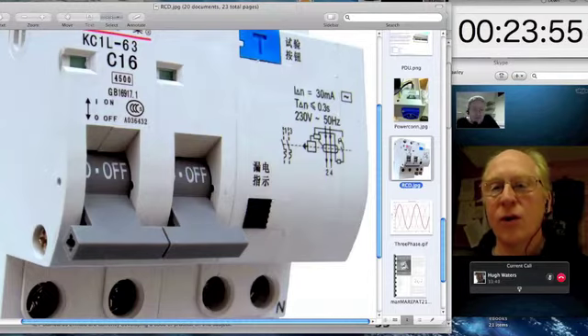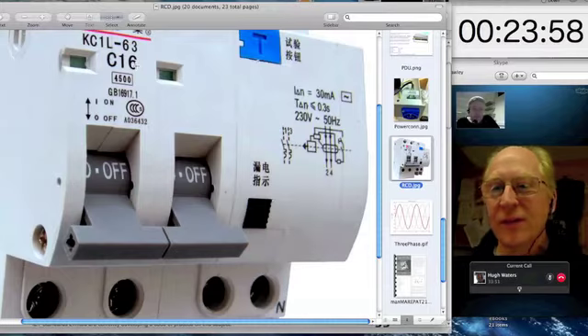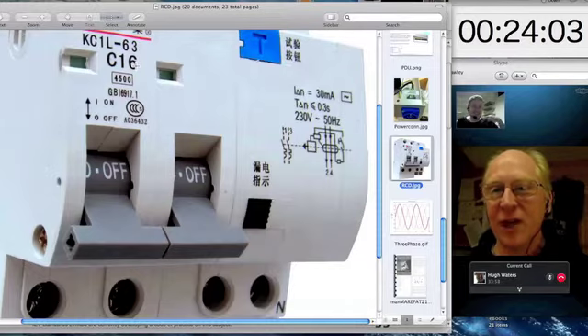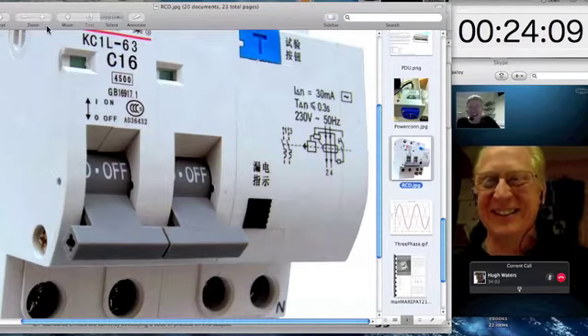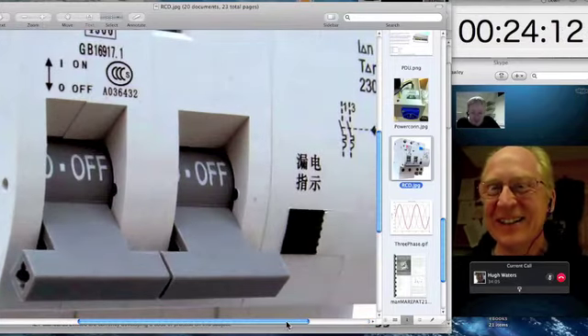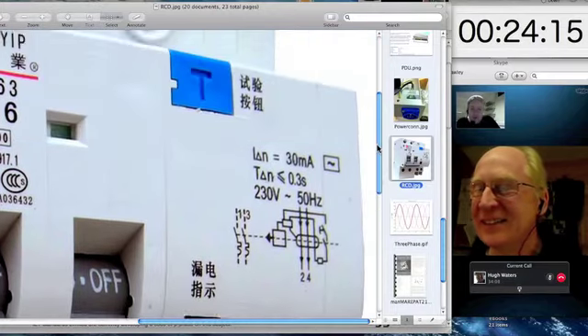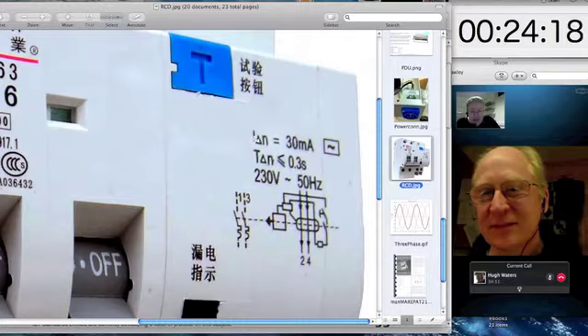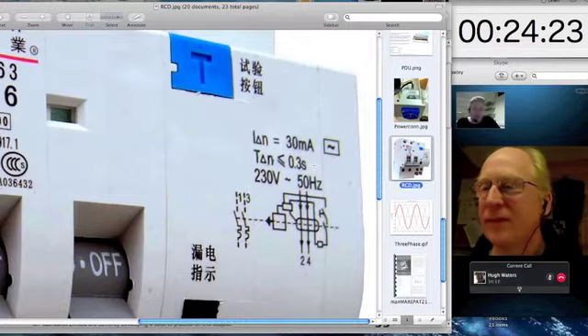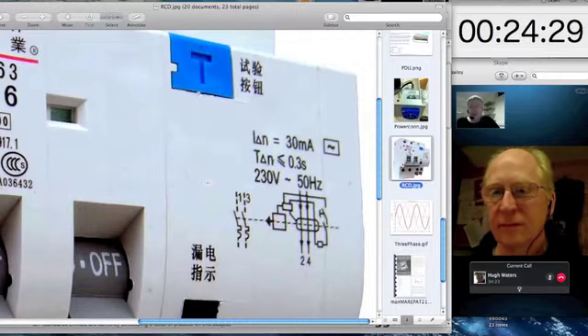And so if you had your hose analogy, you've measured the amount of water going in, you've measured the amount of water coming out. Oh, hang on, less is coming out than is going in. Yeah, therefore there must be a leak somewhere. The floor's getting wet. Got wet trousers. Yeah. And so I'm zooming right in on this, and you'll see that the marking on this RCD is I differential n, so a current difference of 30 milliamps, and T differential n less than 0.3 of a second, 300 milliseconds. So that's basically saying if we see more than 30 milliamps of residual current for more than 300 milliseconds, we break the supply.